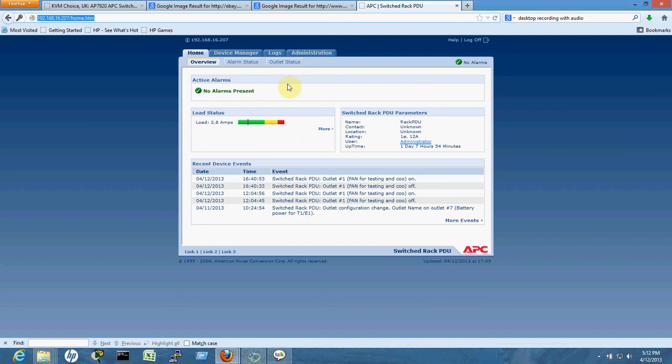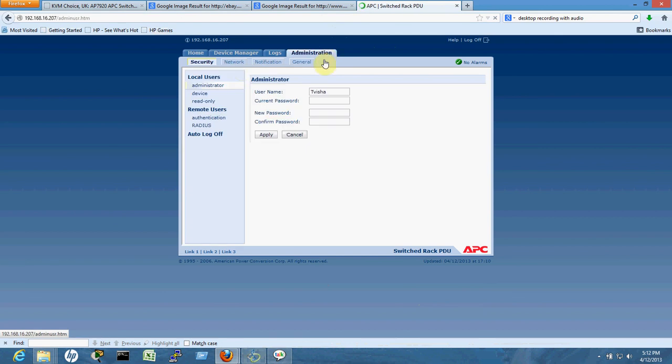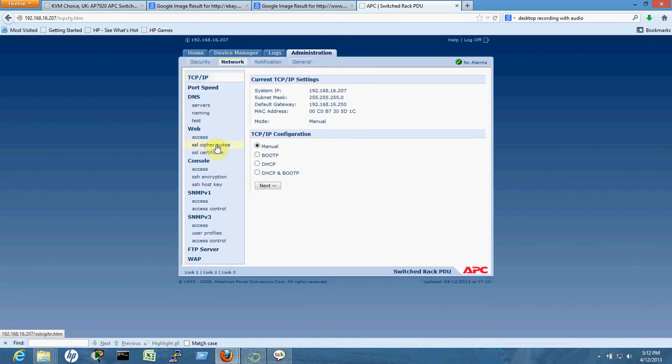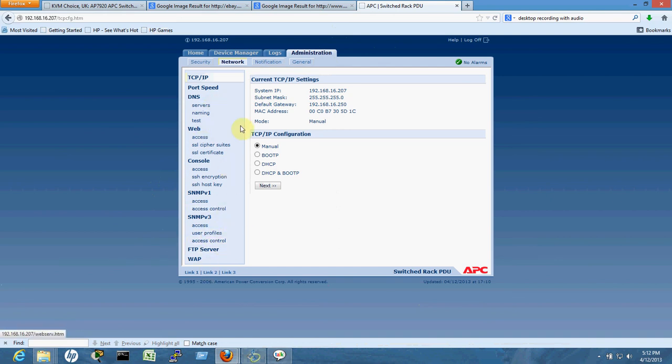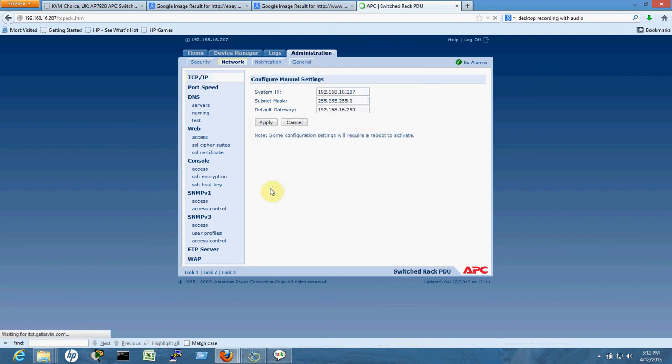I went into the administration, then to the network settings. There you'll see something called manual mode, where you can modify the IP address to whatever you want from your pool, along with the subnet mask and default gateway. The APC automatically takes the default gateway when you plug it into your network.